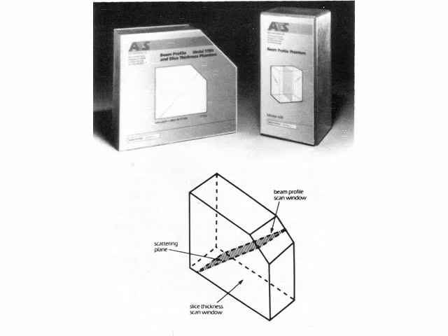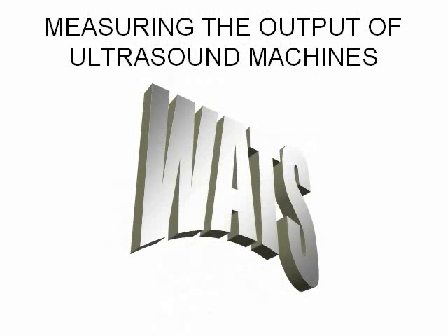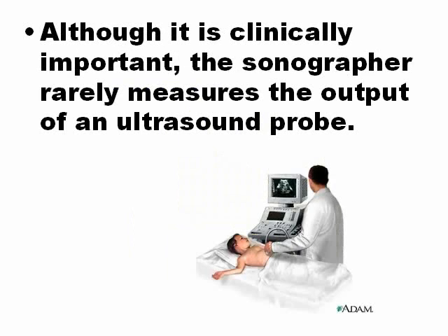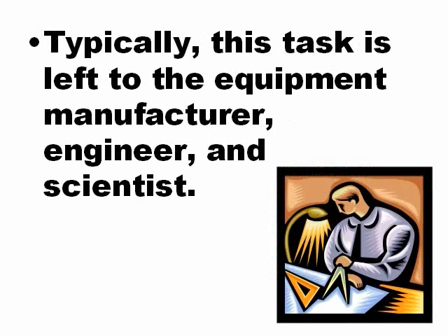This kind of slice thickness phantom is more used in the factories where ultrasound machines are produced. Measuring the output of the ultrasound machine is very important, because that lets you know that the machine is safe. Really, measurement and quality assurance are very important, but it's not the sonographer who measures the output of an ultrasound probe. This is more about technicians, engineers, and factories that produce ultrasound machines. This kind of testing is for the manufacturer and not for technicians.